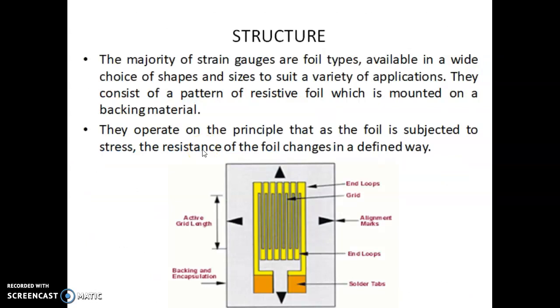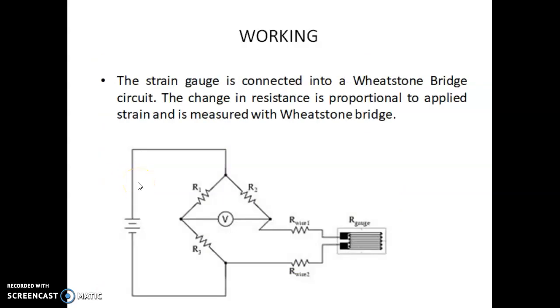The structure of a foil type strain gauge is shown here — the majority of strain gauges are foil types. They operate on the principle that when the foil is subjected to stress, the resistance of the foil changes in a defined way, and this resistance change is used to measure the strain. A Wheatstone bridge is used: one or all resistances are replaced with strain gauges. The change in resistance due to elongation is reflected as a change in voltage by the potentiometer, which is calibrated to give the strain value.